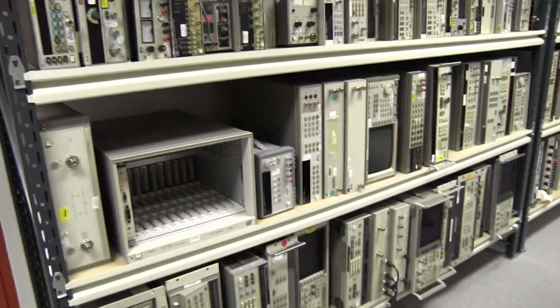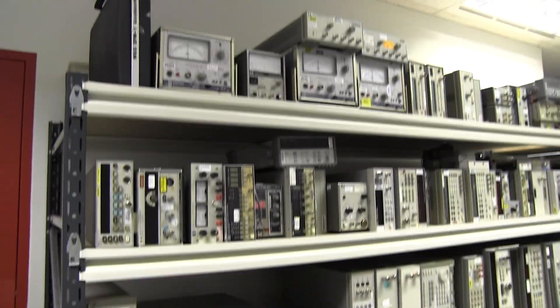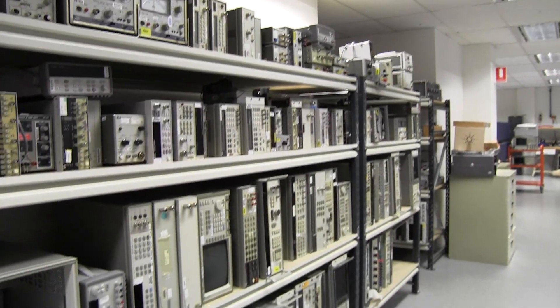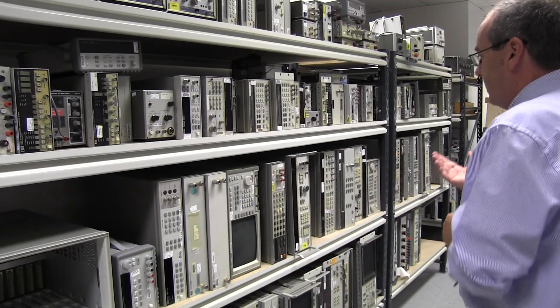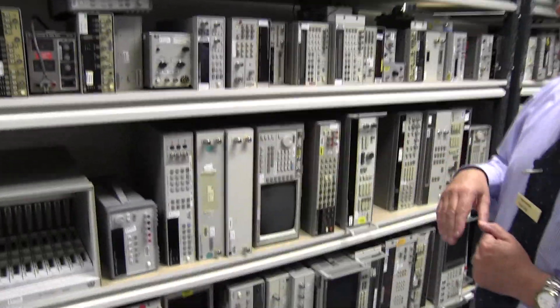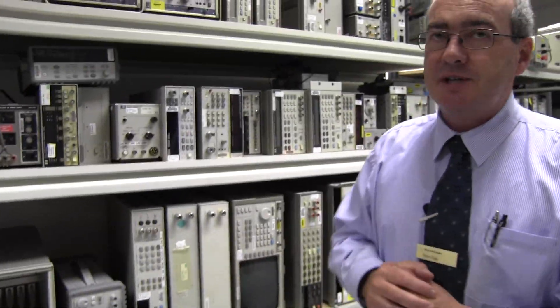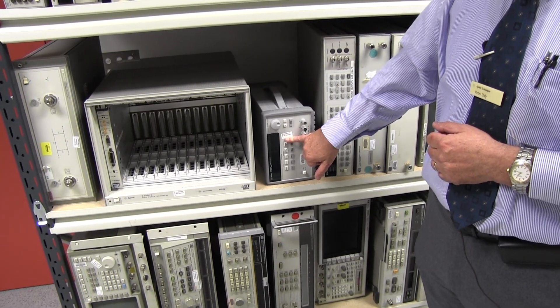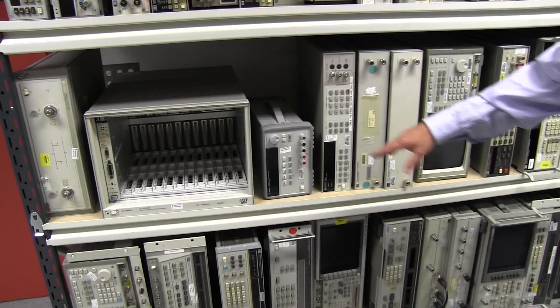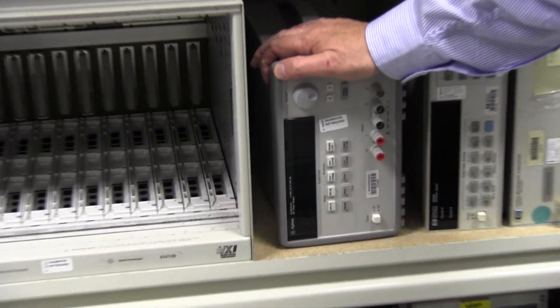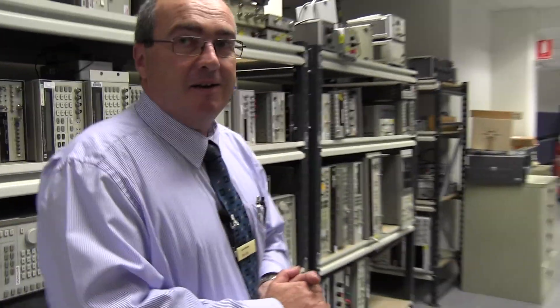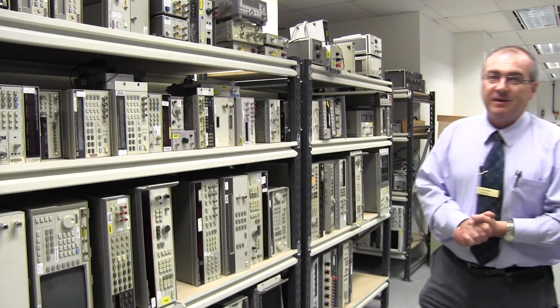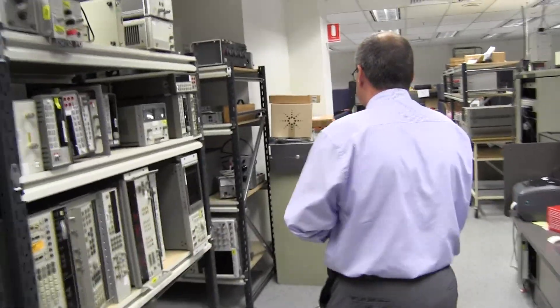Here's a whole bunch of gear - some old stuff, some current stuff. This is general purpose test equipment, still calibrated. This is lab gear that's left over. The stuff that's not in use has got a quarantine sticker on it. We even calibrate power supplies. Some people need their power supplies calibrated - it's part of the standard if you're doing switching systems for data. You need a switchable power supply and load generally matched for it.